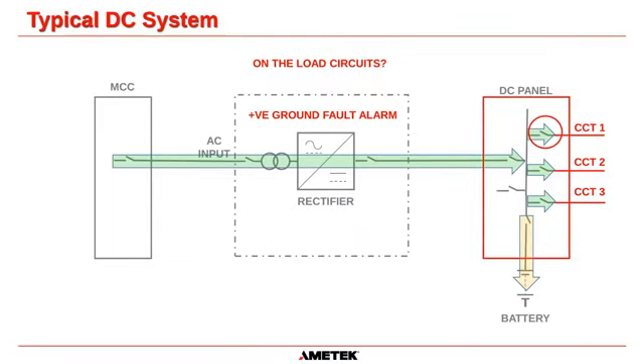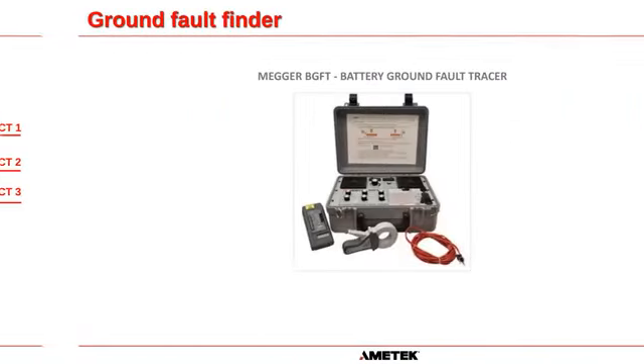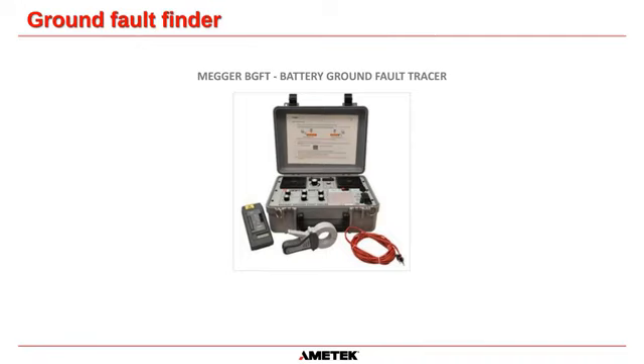Okay, this one here is saying open circuit 1, open circuit 2, or open circuit 3. Find out which one clears the fault. That's the most unscientific way to do it. The most scientific way to do it is to buy a ground fault detection system. And the most popular one in the US is the Megger BGFT, the Battery Ground Fault Tracer. And this picture on the screen shows you exactly what it looks like.